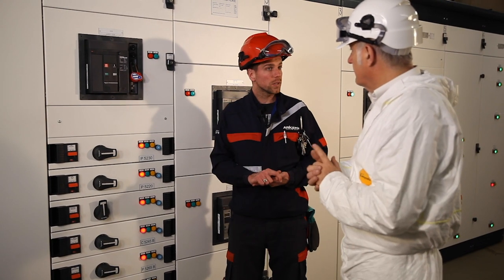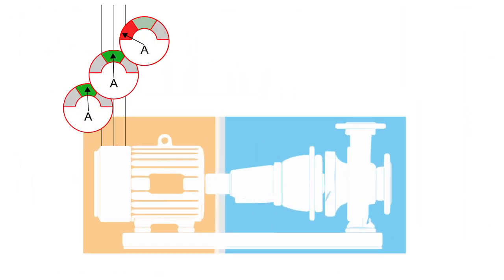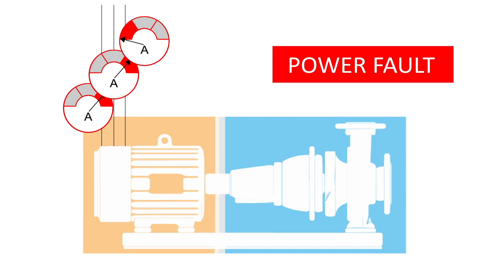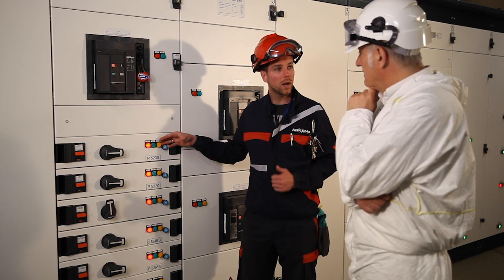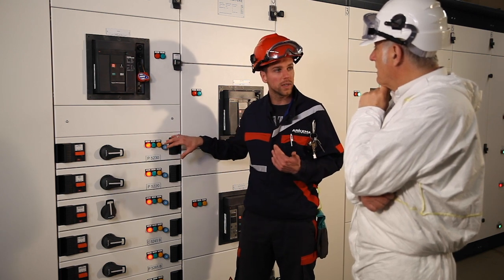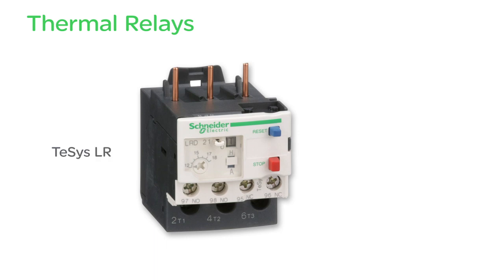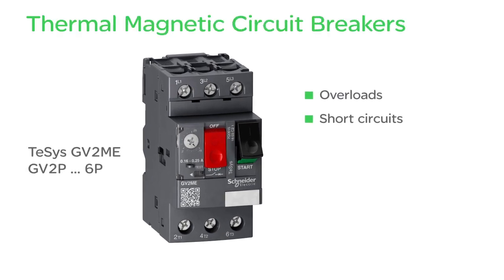The third challenge is the absence of a phase — the loss of power supply. The current of the other two phases will increase. The overload protection provided by the thermal relay will trip the contactor. The failure will be relayed and sent to the supervision screen with the possibility of resetting on phase return. The thermal relay protects against imbalances and phase absences when the motor drives its normal load. Thermal magnetic circuit breakers also monitor phase loss.